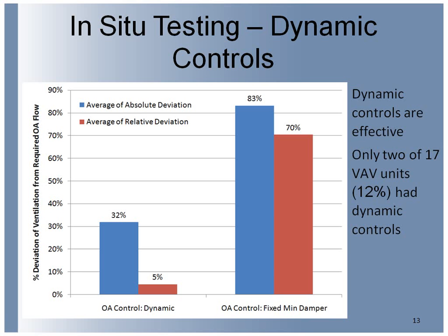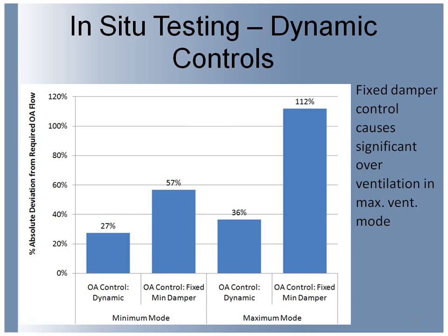So one of the important things that we found through this study, and is kind of somewhat addressed in the code, although not universally, is this notion of dynamic control of the minimum ventilation. So we're talking about just the minimum outside air ventilation. And for those systems that have dynamic controls, we find what we would expect, that we have a lot less overventilation than those that just have fixed minimum damper positions, which is the predominant system type in the world. We're talking about a factor of 3 times more overventilation, at least, for those systems. And if you dig into it a little further, the data become even, I think, a little more compelling in terms of what we need to do as an industry.